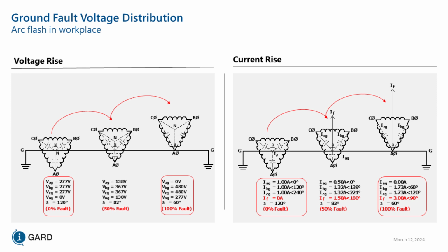So if you look at this particular schematic between A phase, B phase, and C phase on the voltage on the left-hand side, you have capacitive coupling from the phase conductors to ground. Think of the cable as a distributed capacitor, because you have two potentials isolated from each other by an insulating medium. Well, that's the insulation on your cable. So that's a capacitor, and this capacitor is distributed throughout your entire facility. Those capacitors are charged and discharged when you have a ground fault.